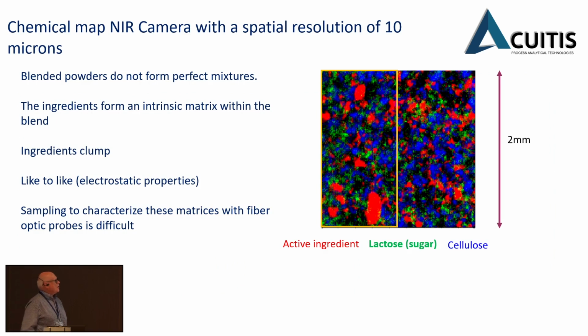Phil talked about this earlier, but the one thing he didn't tell you is that this is 2 batches of the same product. And you can see that one of them is very, very uniform, and the other one is not. And they both pass specification. It is just a factor to do with the batch of raw materials that was used, particularly the API. So they both pass specification, but spectroscopically they're going to give you quite a different answer. And that's one of the complexities of using these fiber optic probes, that you do have to cope with the matrix not always being completely the same.